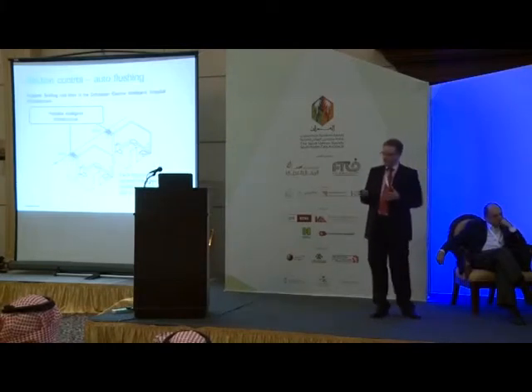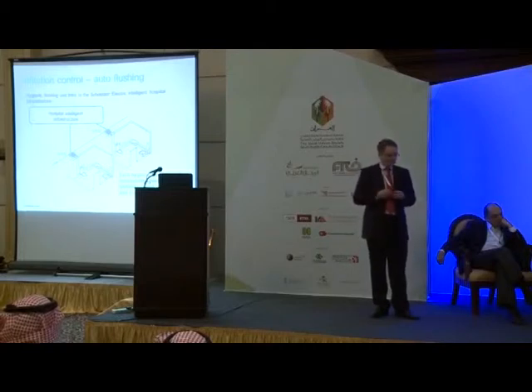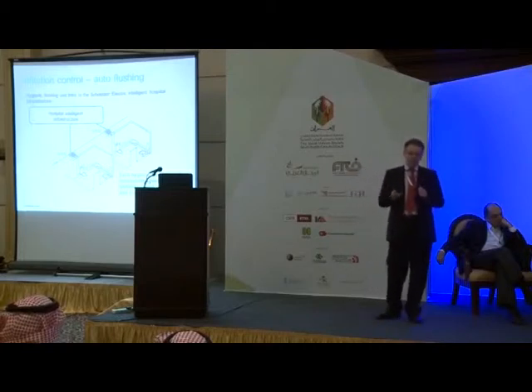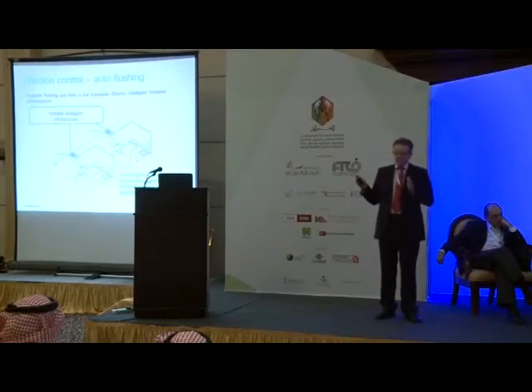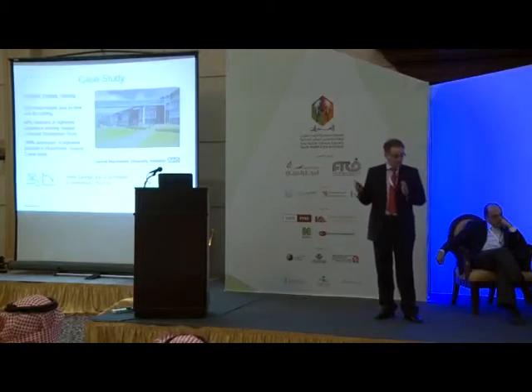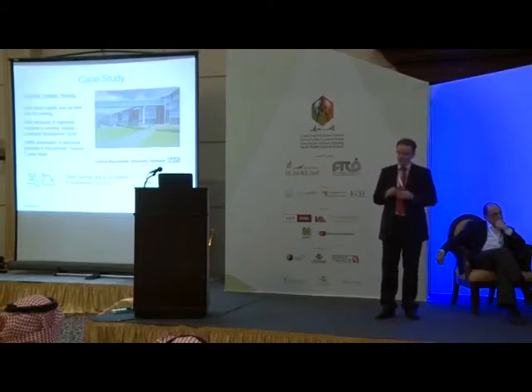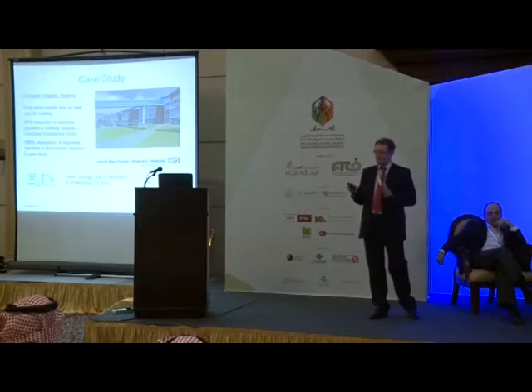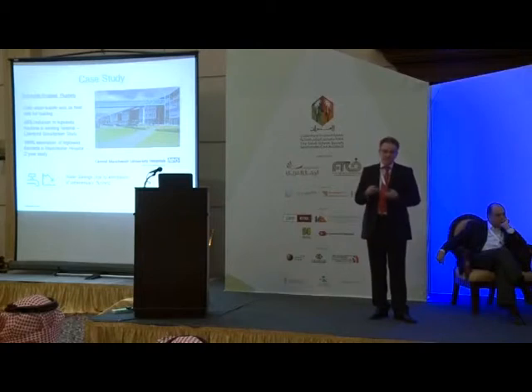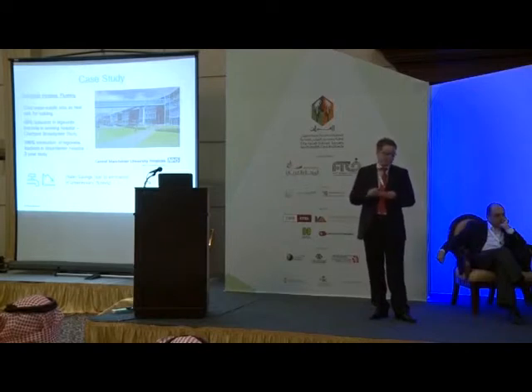Another good form of infection control is automatic flushing systems, combining intelligent valve technology and pressure control, which eliminates the possibility of Legionella buildup in water systems. There was a bad outbreak in the UK at a hospital in Liverpool, where installing the system achieved a 40% reduction in Legionella. A further ongoing pilot study is underway at a hospital in Manchester, where so far no Legionella has been detected since installation in a new hospital building.